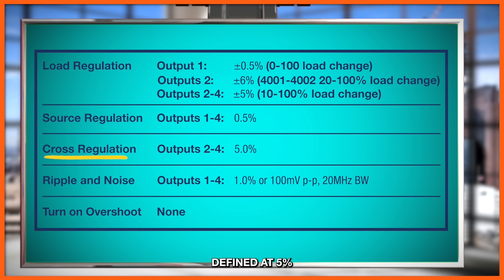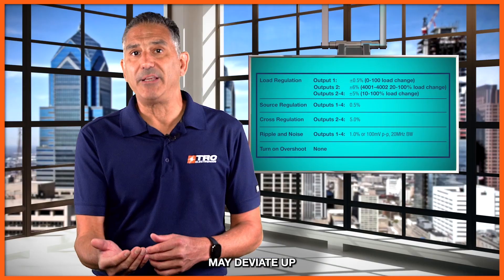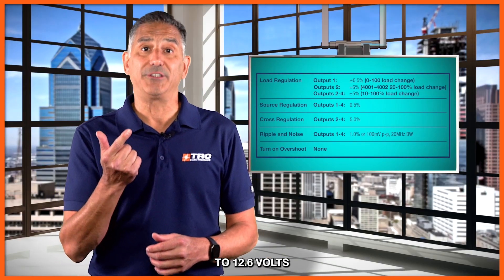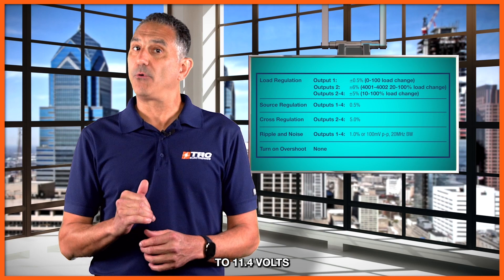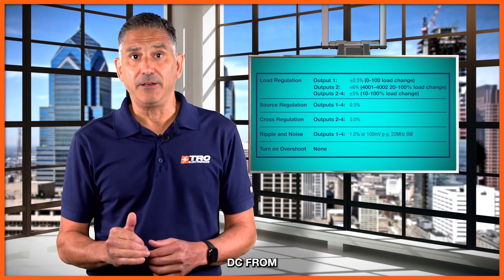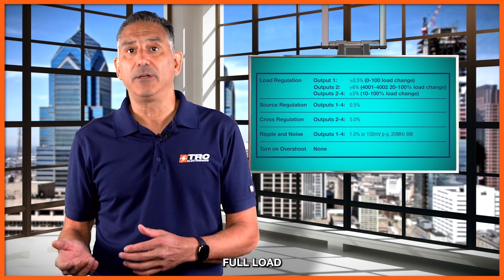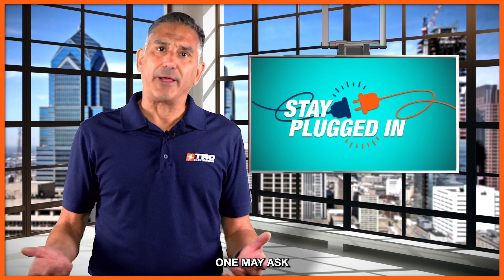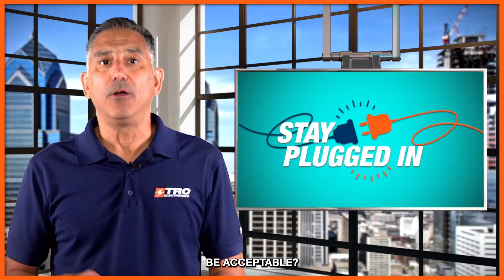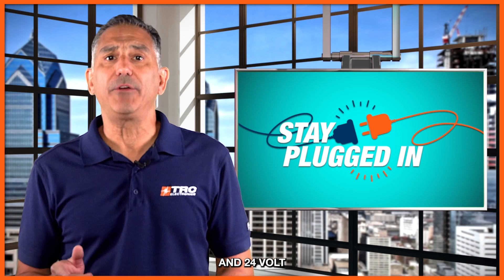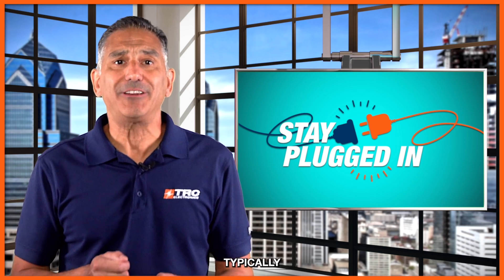You will notice that the cross-regulation is defined at five percent between outputs two, three, and four. This means that a 12-volt output may deviate up to 12.6 volts or down to 11.4 volts DC from a light load to full load on the main output.